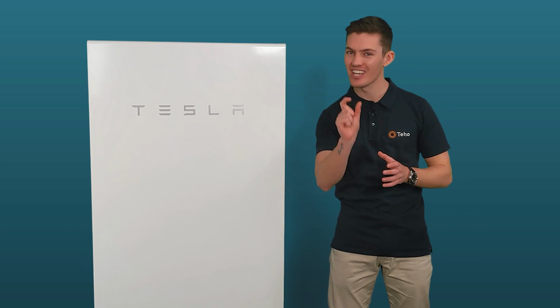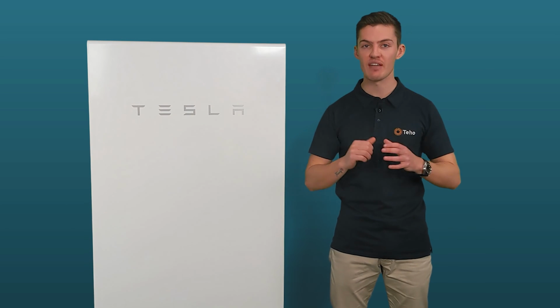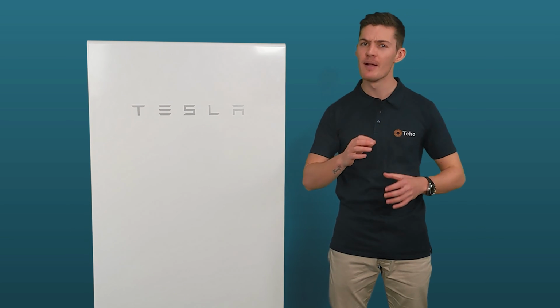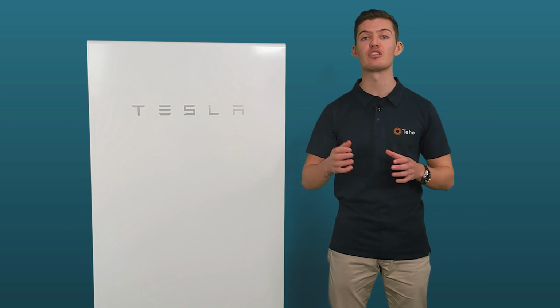Where it can get slightly confusing is in the next section. It talks about if you use Tesla Powerwall for what they consider to be any other application or combination of applications, the warranty will change a little bit. They will still guarantee 70% at the end of the 10-year period, but it will have a 37.8 megawatt hour aggregate throughput cap. The aggregate throughput cap just limits the warranty period, so you can't pump through cycles all day, every day, and still get the same warranty. It'd be like giving a taxi driver the same unlimited kilometer warranty on a car. They will do exponentially more kilometers than your average Joe.